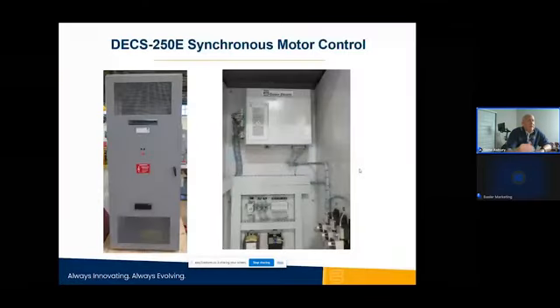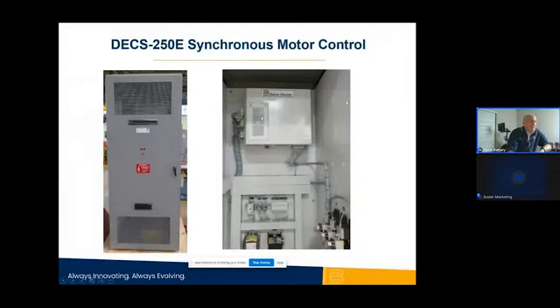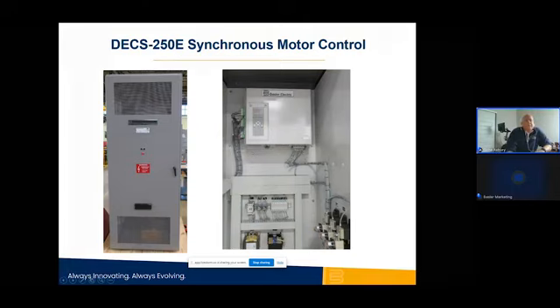Static solutions. When you need more than 15 amps or more than 20 amps, when you're working into slip ring motors, the DECS-250E is ideal. It can go up to 200 amps along with the right power transformer and the right field application relay, field contactor. We can make some very nice synchronous motor units for slip ring motors that will need anywhere from 50 to 200 amps. We've done a lot of work with the water districts out west on their large synchronous motors driving pumps.